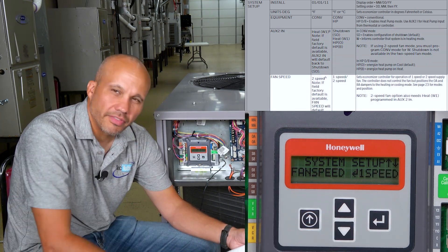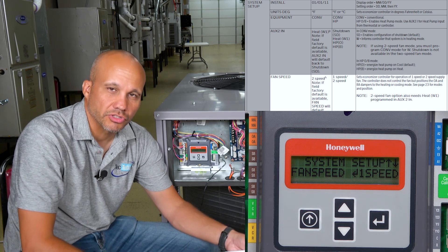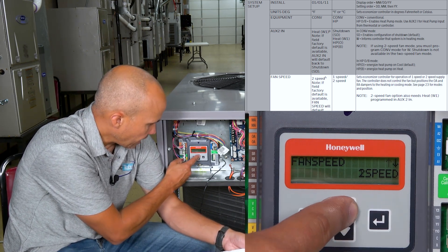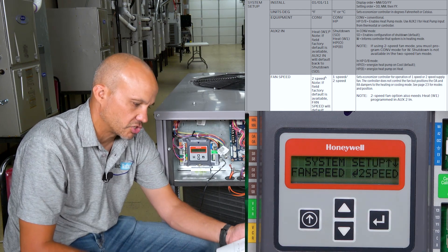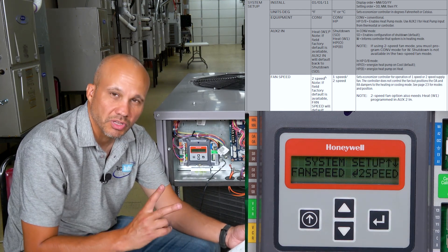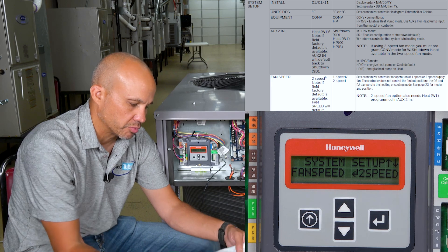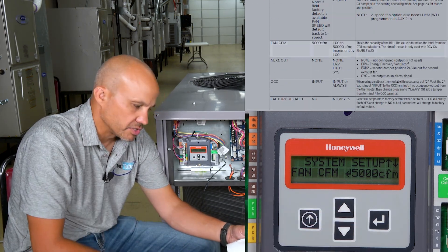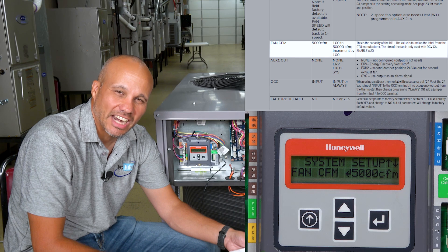Scrolling down to Fan Speed — one or two. I just said most units are two-speed fans, so I'll hit Enter, toggle that up to Two Speeds, hit Enter, and it says 'Change Stored.' Now it's set up for a two-speed fan, which means I'll have two minimum damper positions, which we'll talk about in a second.